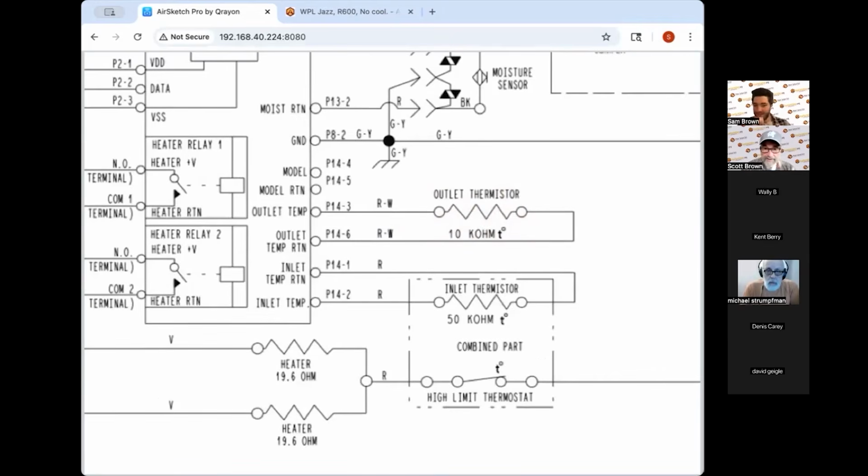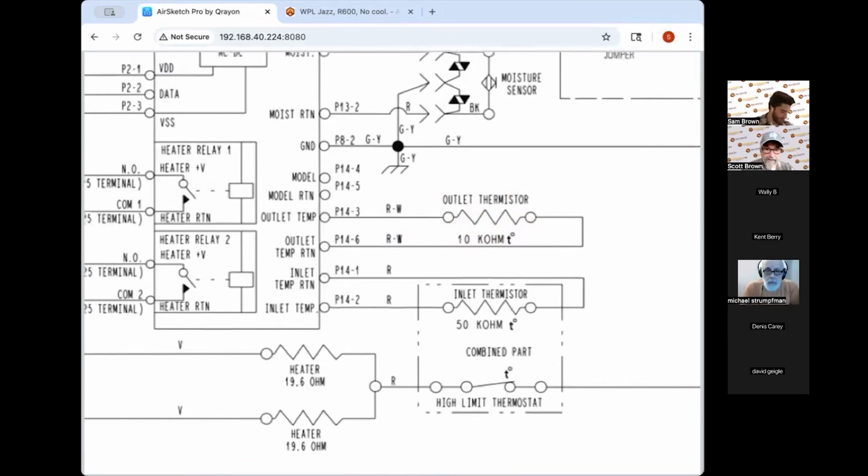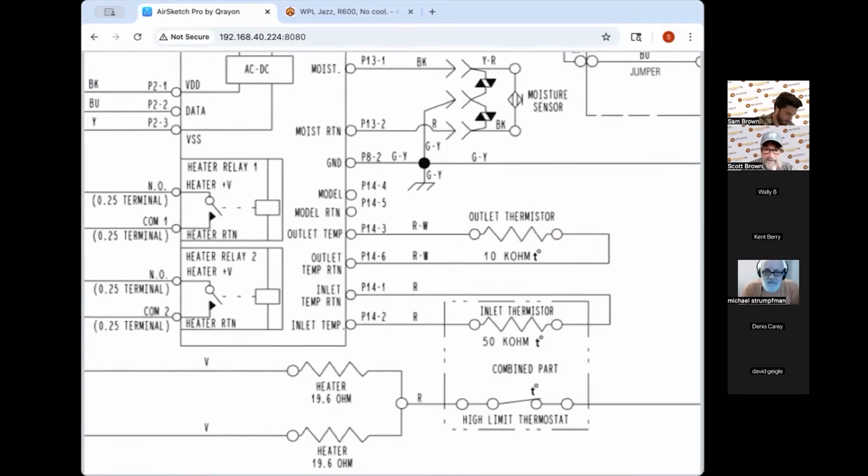Where am I going to test the thermistors? On the main board. Absolutely. Again, using the schematic as your roadmap, you just follow the lines back to the board where it connects. Ohms measurements are made on a dead circuit. I always like to isolate the thing I'm testing from the rest of it, so I don't get the possibility of weird readings back through the board, since they're not showing me what's going on in the board.